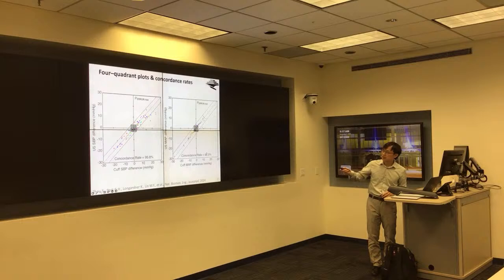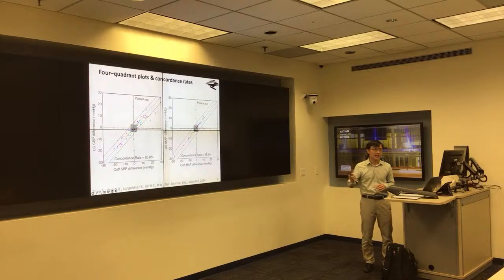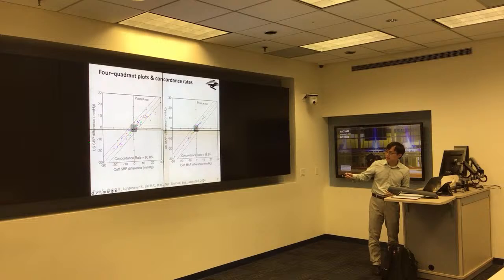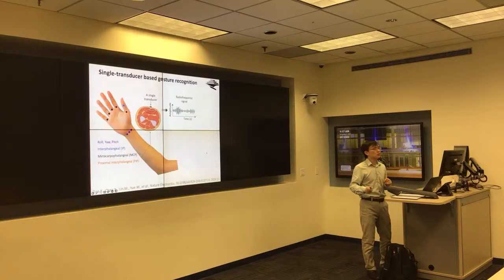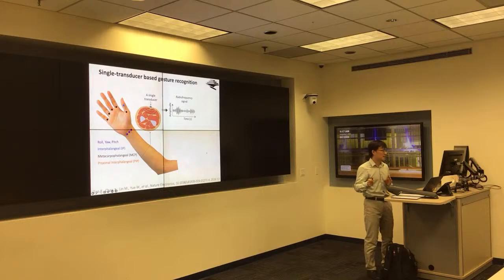So when you compare the readings between the ultrasound measurement and the cuff measurement, ideally those data points should fall on this diagonal dashed line. This is the ideal, perfect case. But in reality, those data points fall within plus or minus 5 millimeters of mercury difference from each other, and that is under this FDA regulation. So this is the systolic blood pressure and mean arterial pressure. We can also do the same thing for the diastolic blood pressure. So ultrasound can do lots of modalities, and one modality is called the A mode.